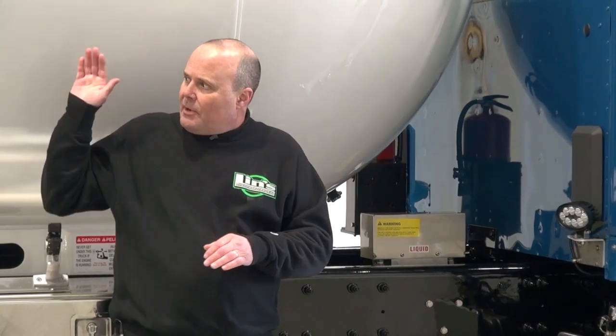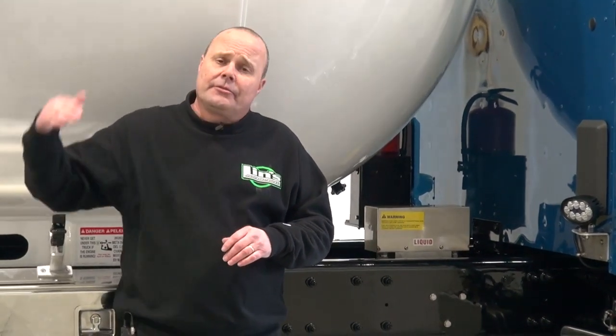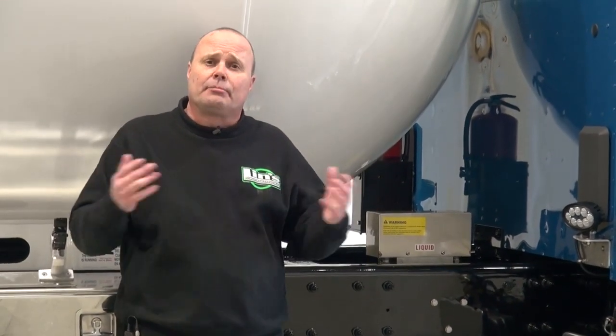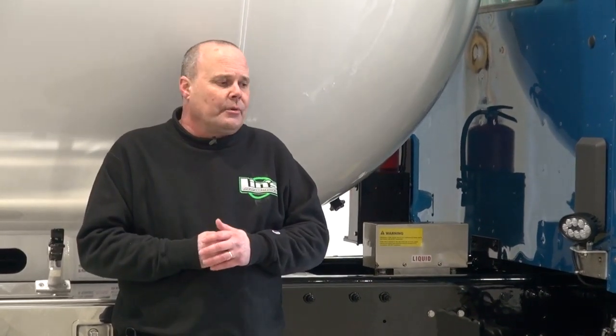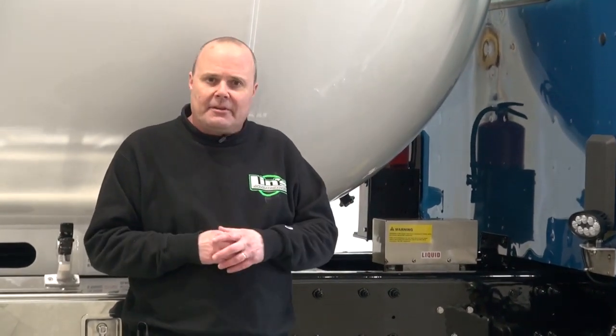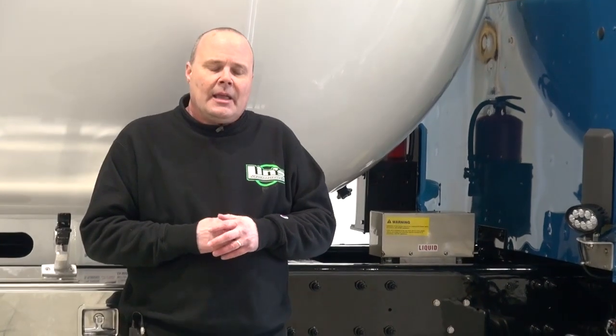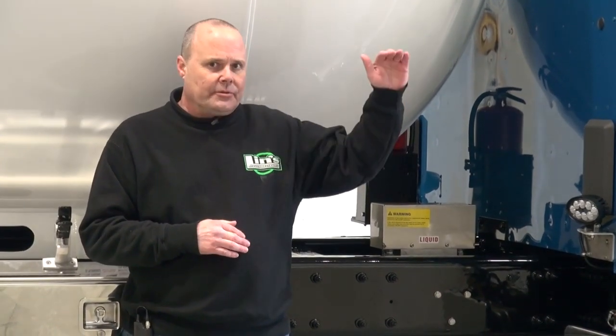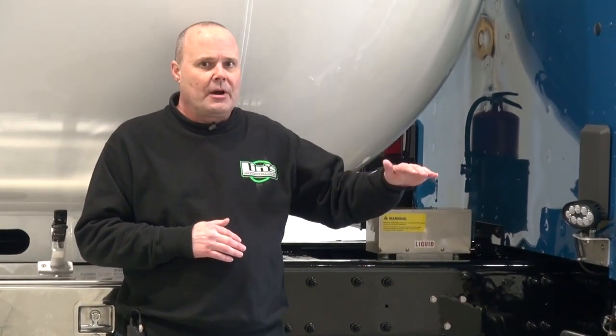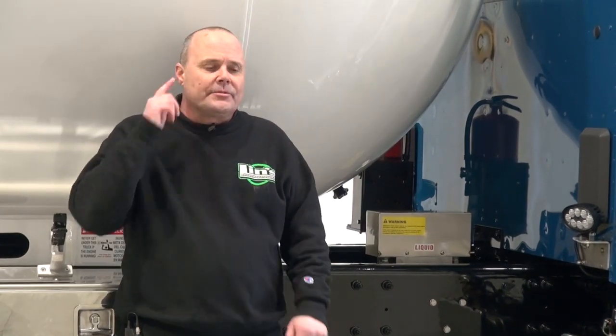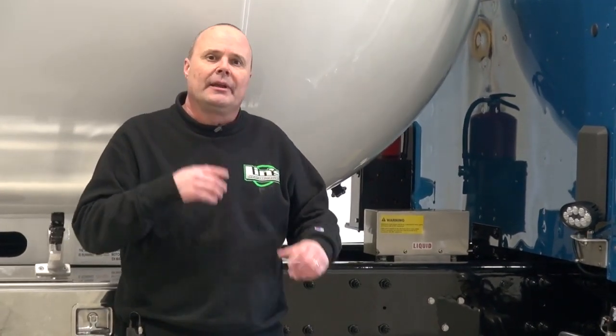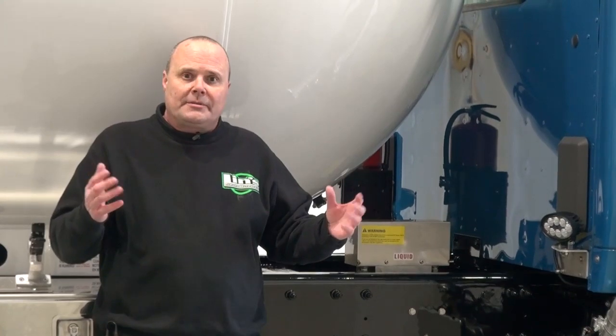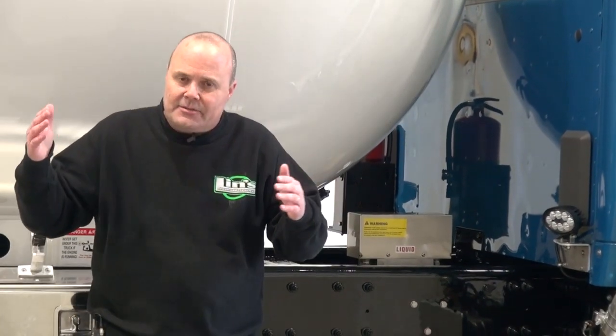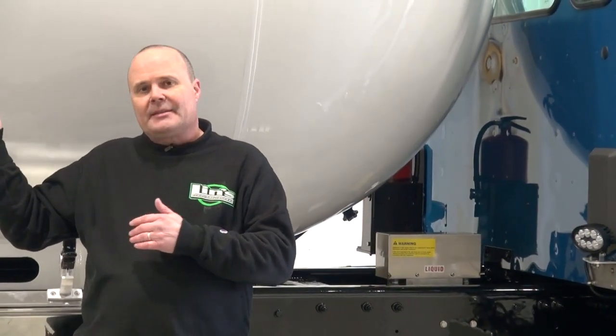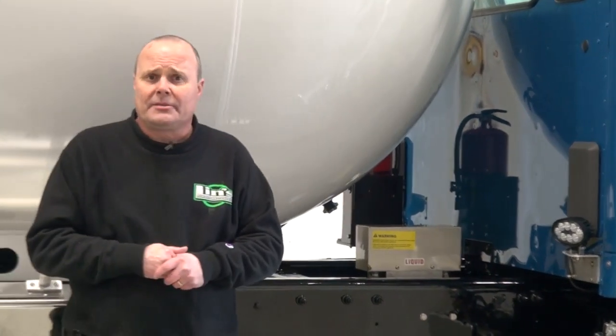As soon as you start pumping liquid off the tank, you're dropping the pressure in the tank, causing the propane to boil. So we've all been out in the field delivering to a 500 or 1,000 gallon tank. As that delivery progresses, you'll steadily see the gallons per minute drop. In addition to that, you'll start to hear that pump get louder and louder. Why does it do this? As you're pumping the gallons off the truck, the pressure's dropping in the tank, causing the liquid propane to boil.